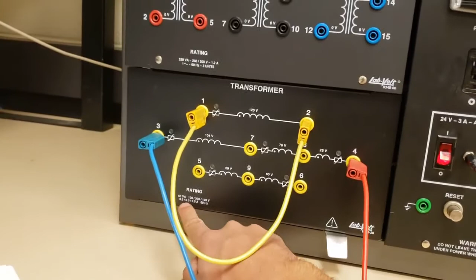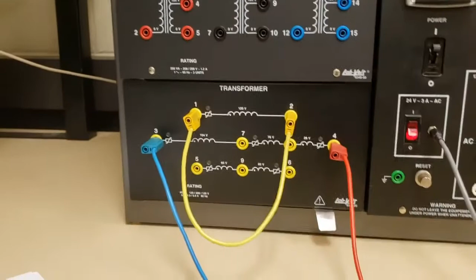So you're going to raise the voltage very slowly, and you're going to find the current rising really quickly because the other side is short circuited. And so raise the voltage slowly until you see the rated current, and then you're good to go. A note: the rated current is not immediately apparent on the transformer on the module itself, and it's also usually not directly apparent on the nameplates of transformers you might see outside. And that's because you should be able to, on your own, calculate what the rated current is. You know the power rating, you know the voltage rating on the secondary or the primary or whatever it is. You can calculate what the rated current is easily. So that should be something you can calculate on your own.